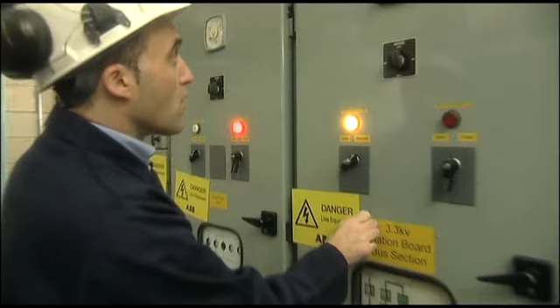Step 3. Protect against any other live parts. Protection can be in the form of warning notices attached to all the panels that are not going to be worked on. Flame-proof overalls should be worn. Additional physical barriers, such as locks and insulating screens, must be applied if the live equipment is exposed. By clearly identifying the nearby parts, which must not be touched, you are also helping maintain Step 1. You then need to recheck that you have the correct point of work.